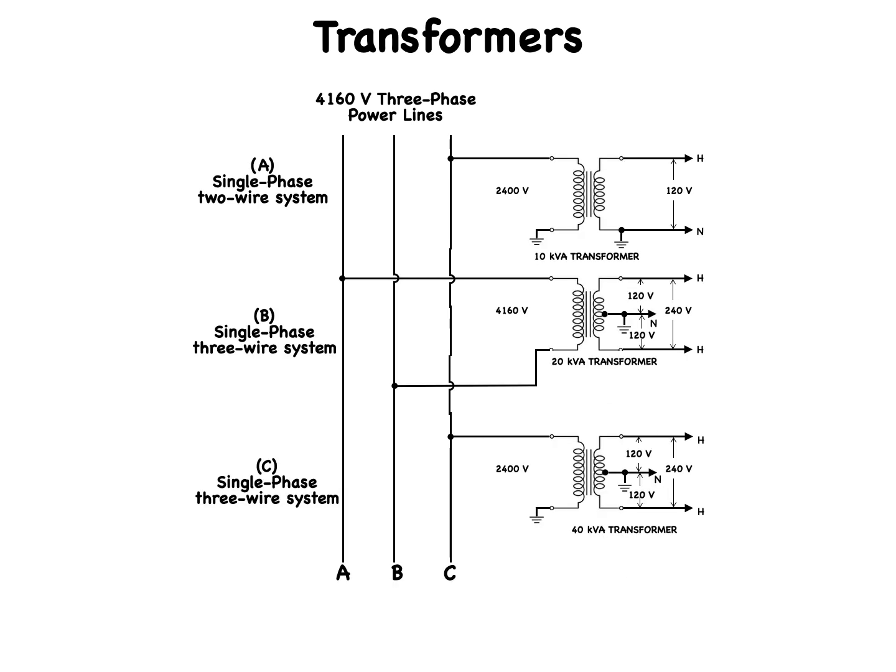Single-phase systems can be of two major types: a single-phase two-wire system, shown in A — the top diagram — or a single-phase three-wire system, shown in B and C — the middle and bottom diagrams. These systems are shown here as 10 kVA, 20 kVA, and 40 kVA transformers whose secondary produces single-phase voltages of 120 and 240 volts.